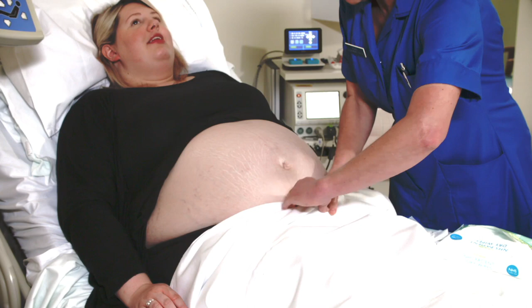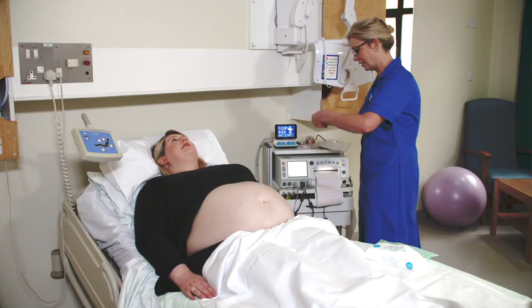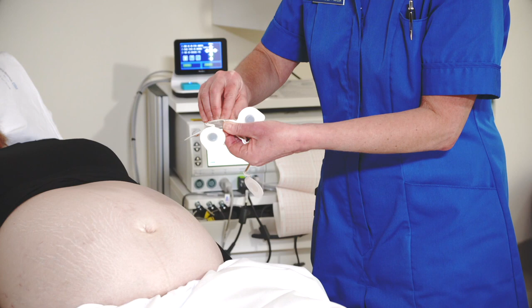Before you start, wash and dry the abdomen where the patch will be placed. This will remove any ultrasound gel or lotion the mom has been using to ensure the electrodes stick down. You can open the patch packet by tearing along the top edge following the pre-cut slits. Remove the patch, discarding all of the packing materials, and then remove the protective film covering the adhesive pad on the back of the plastic clip.